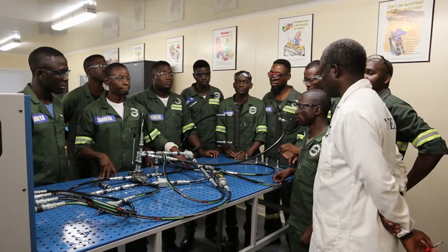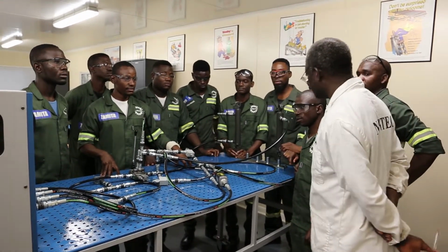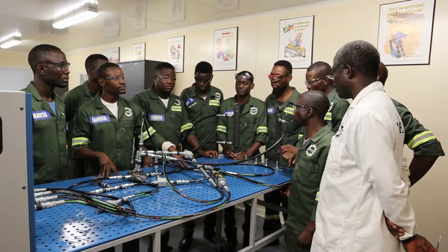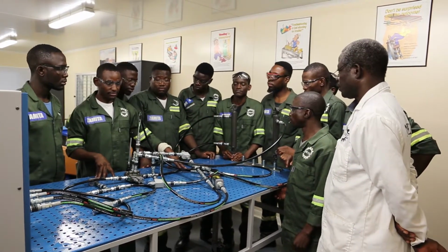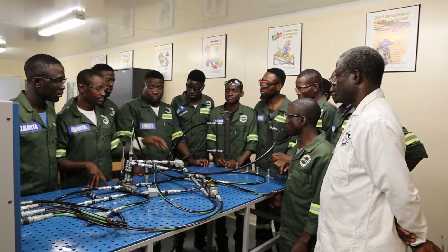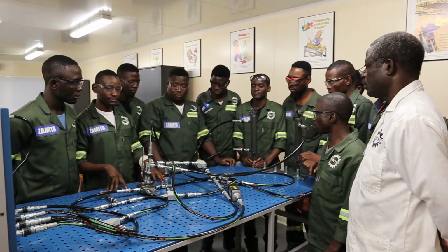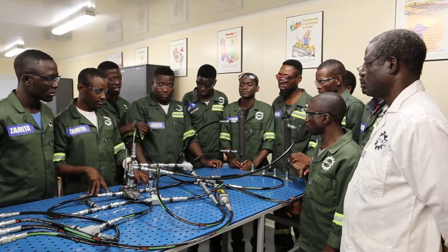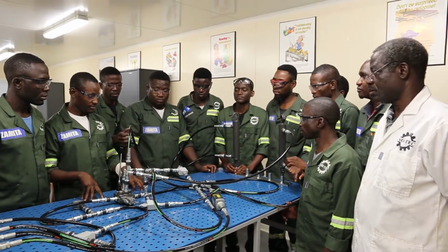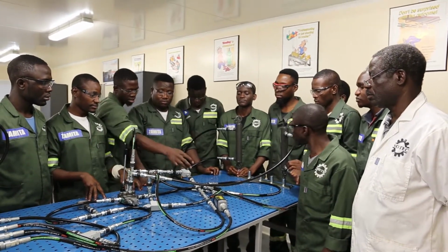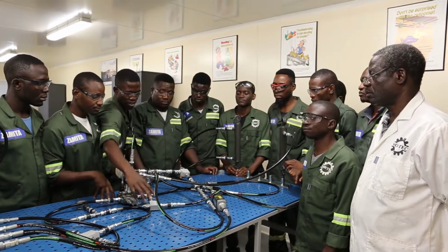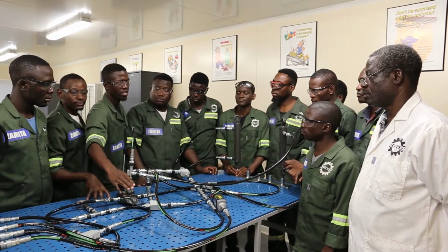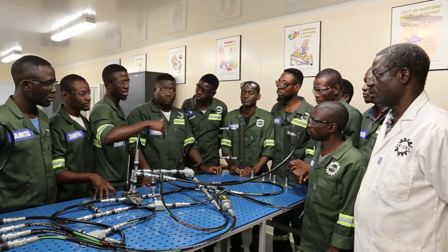Thanks very much. I hope any challenges from the others, any comments so far? I think just to add on to what my colleague has said concerning the prioritizing of the cylinders when retracting and extending. On the part that we had a challenge first, we had set these two relief valves at the same pressure. That gave us a challenge on retracting.